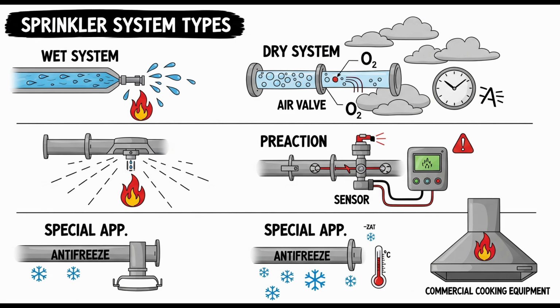Moving outside the building now, let's look at outside sprinklers for protection against exposure fires. This isn't about fires inside the building, right? Correct. This is about protecting a building from a fire happening next door or from some other nearby external fire hazard, like a wildfire approaching or a large fire in an adjacent structure. These are sprinkler systems installed deliberately on the exterior of a building. A water shield, essentially. Yes, the goal is to create a water curtain or thoroughly wet the building surfaces to protect against the intense heat radiating from that external fire. They can be used regardless of whether the building's interior has sprinklers or not.